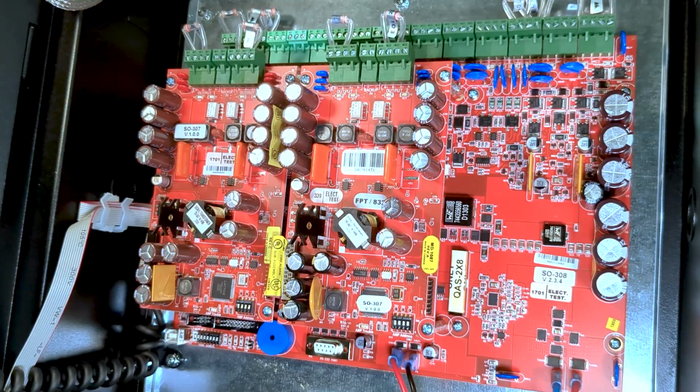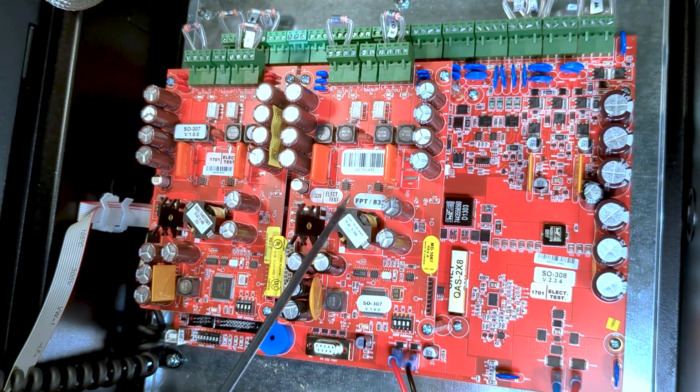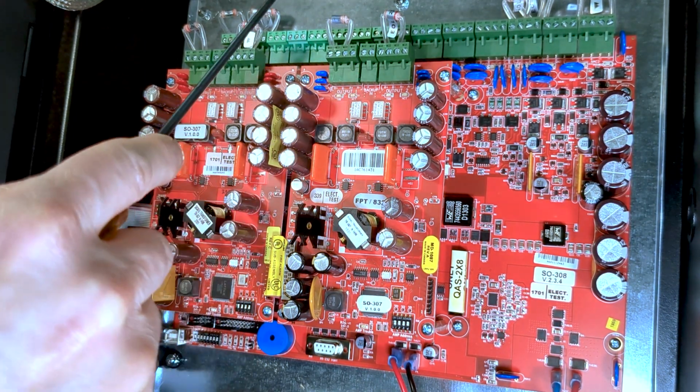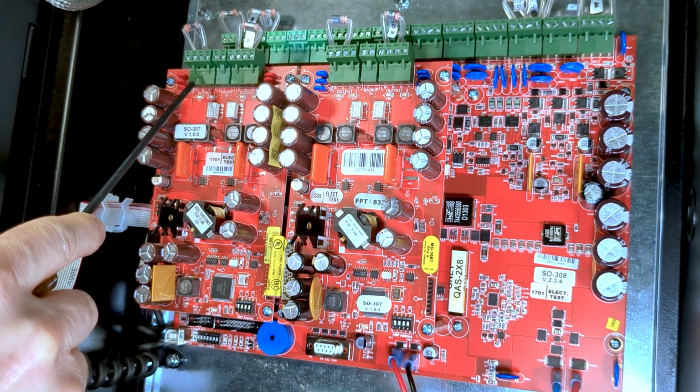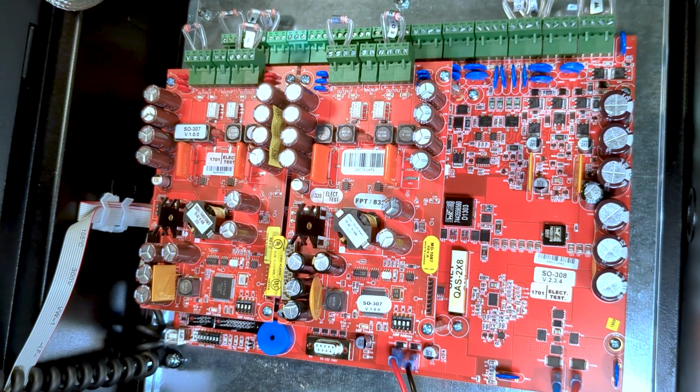Now that we have the second QAD30 installed in P6, we can set our dip switch addresses on the bottom to 1 and 2. We now have provisions to use the second QAD30 as a backup amplifier by connecting the backup input to either A or B output from the first QAD30 amplifier.